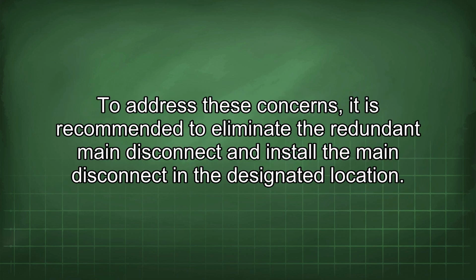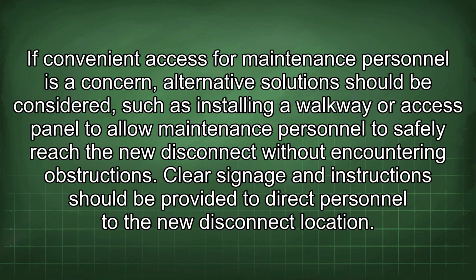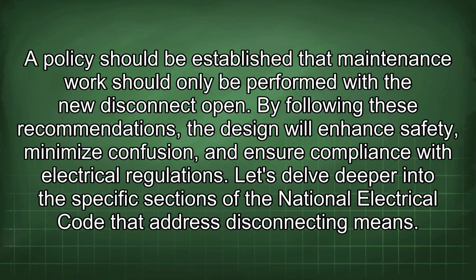To address these concerns, it is recommended to eliminate the redundant main disconnect and install the main disconnect in the designated location. If convenient access for maintenance personnel is a concern, alternative solutions should be considered, such as installing a walkway or access panel to allow maintenance personnel to safely reach the new disconnect without encountering obstructions. Clear signage and instructions should be provided to direct personnel to the new disconnect location. A policy should be established that maintenance work should only be performed with the new disconnect open. By following these recommendations, the design will enhance safety, minimize confusion, and ensure compliance with electrical regulations.